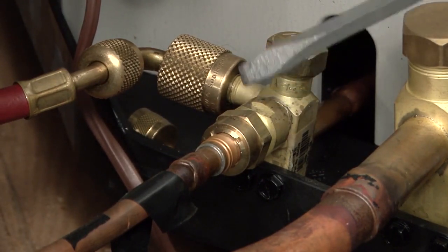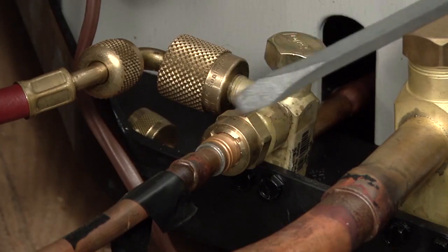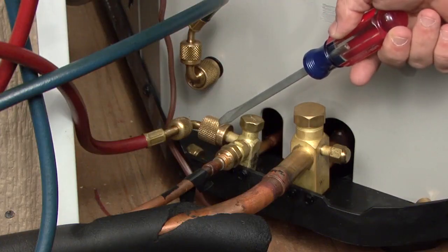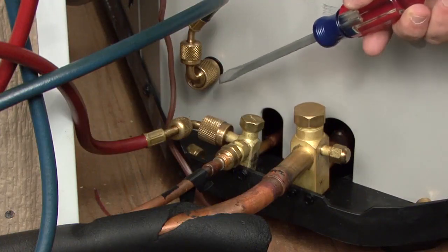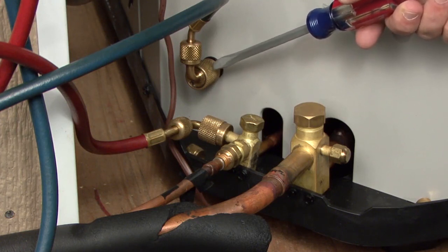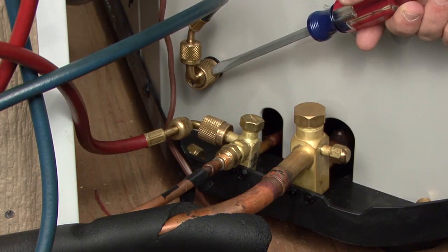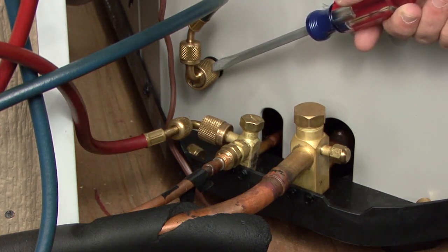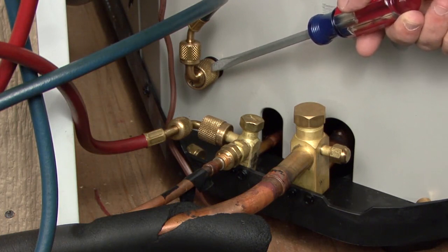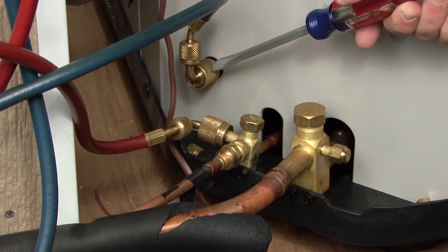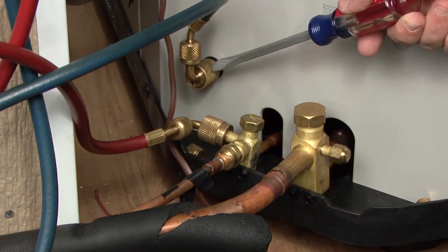Some other things to keep in mind about this service valve. So here we've got our high side connection on the liquid line service valve, and we've got our low side suction on the extra port that we give you for the heat pump, so you can read suction pressure. Now remember, you can read that suction pressure in heating mode or cooling mode. This is always suction regardless of the mode. That's what I mean by that.